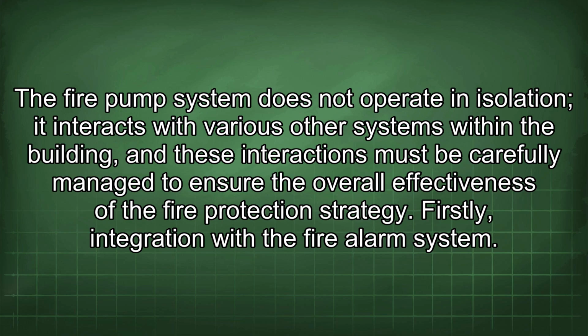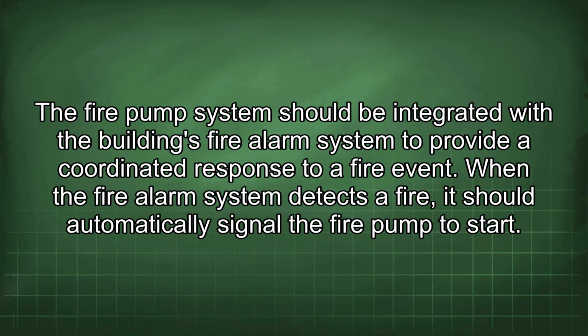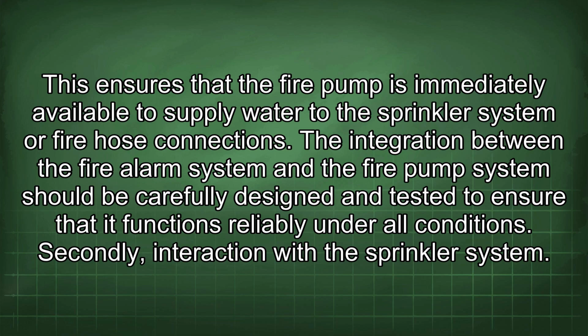The fire pump system does not operate in isolation. It interacts with various other systems within the building, and these interactions must be carefully managed to ensure the overall effectiveness of the fire protection strategy. Firstly, integration with the fire alarm system. The fire pump system should be integrated with the building's fire alarm system to provide a coordinated response to a fire event. When the fire alarm system detects a fire, it should automatically signal the fire pump to start. This ensures that the fire pump is immediately available to supply water to the sprinkler system or fire hose connections. The integration between the fire alarm system and the fire pump system should be carefully designed and tested to ensure that it functions reliably under all conditions.